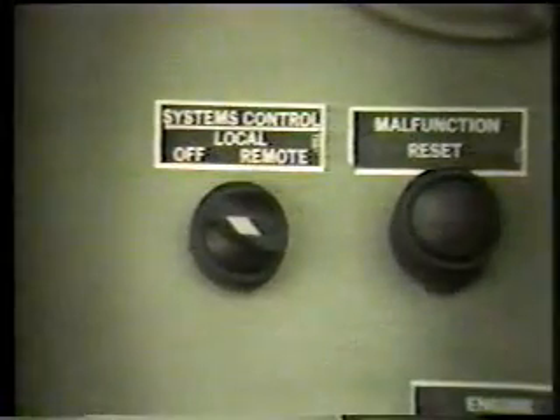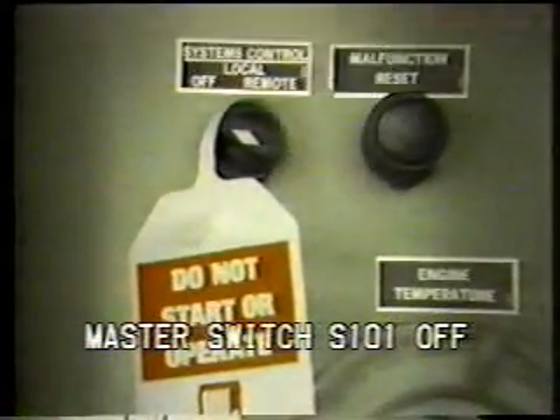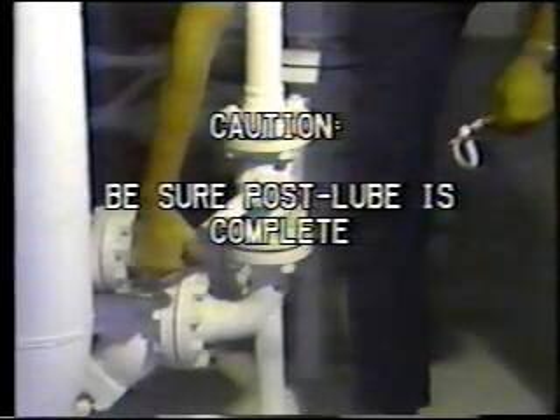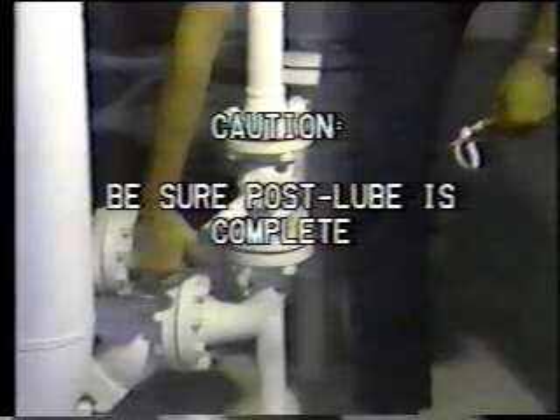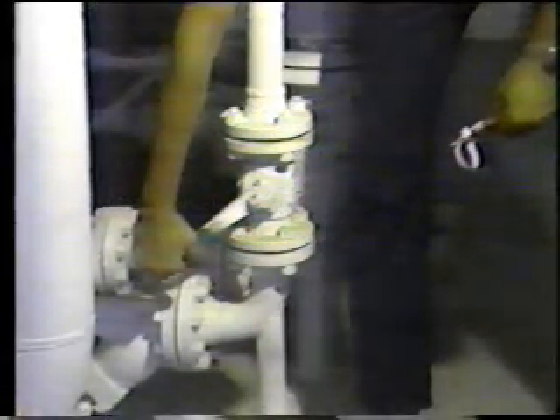Prior to calibrating the unit, shut down the unit. Now turn the master switch off. Then tag the switch. Caution: be sure the post-lube is complete prior to securing the fuel and service gas. Next, secure the gas supply if the package is equipped with a gas fuel or gas start system. Open the door of the control console.